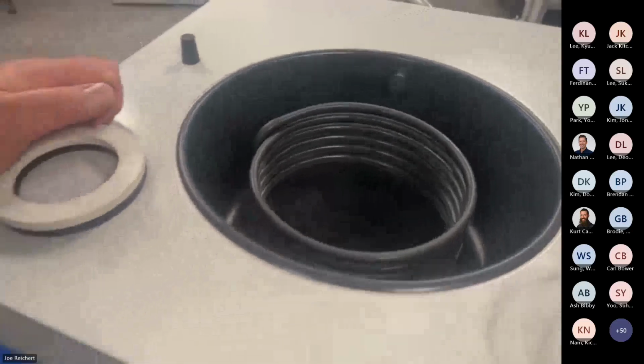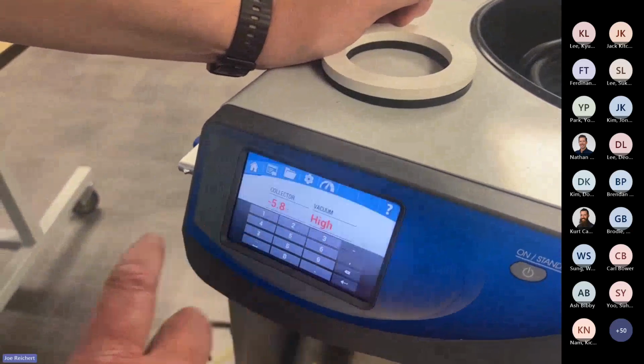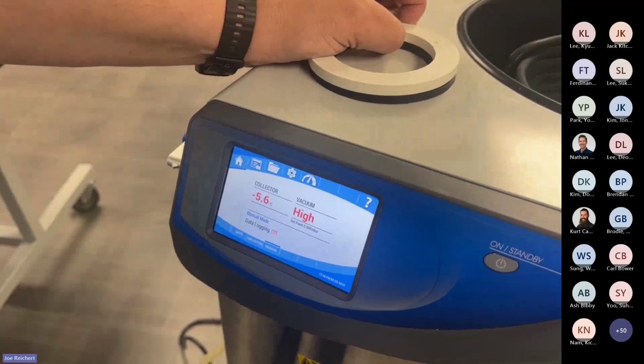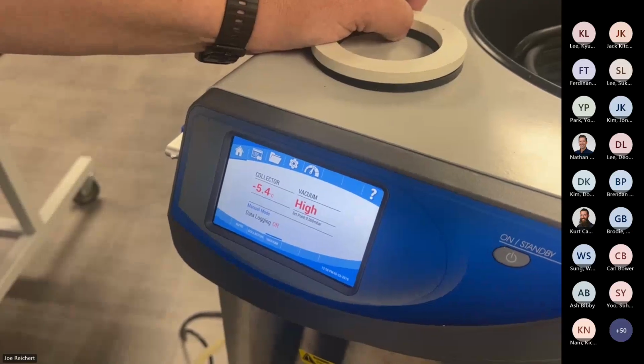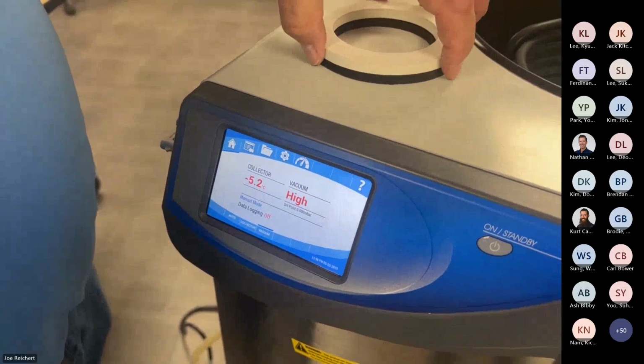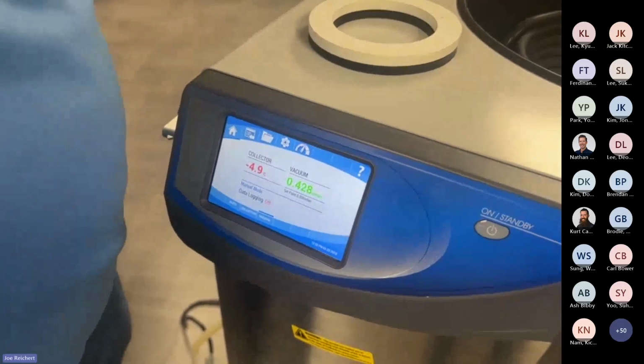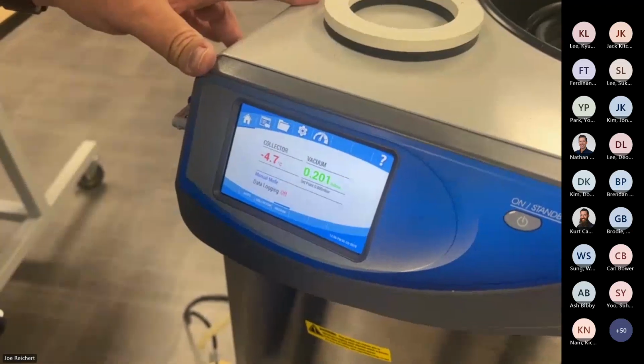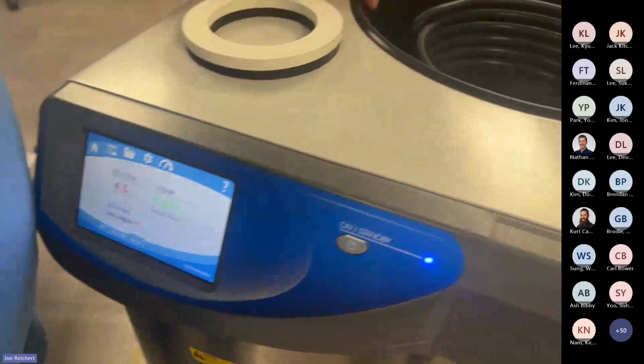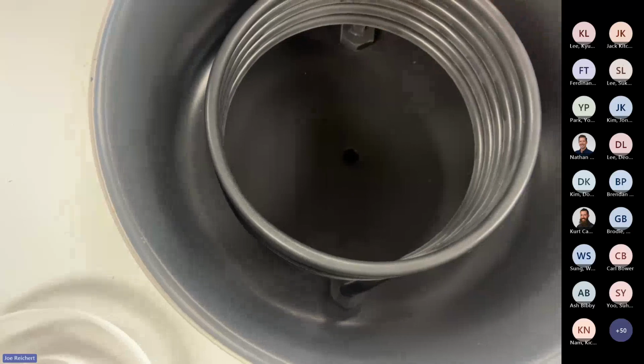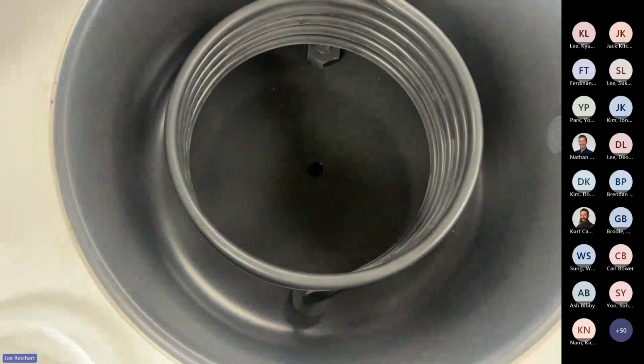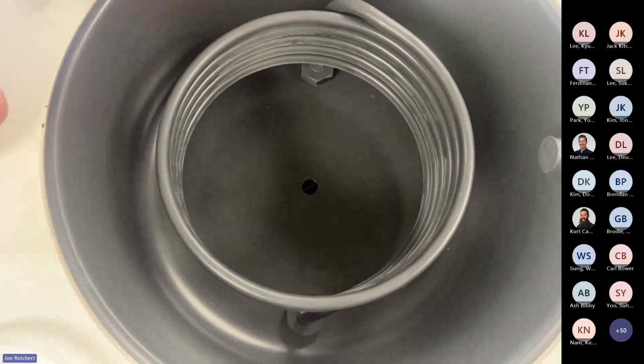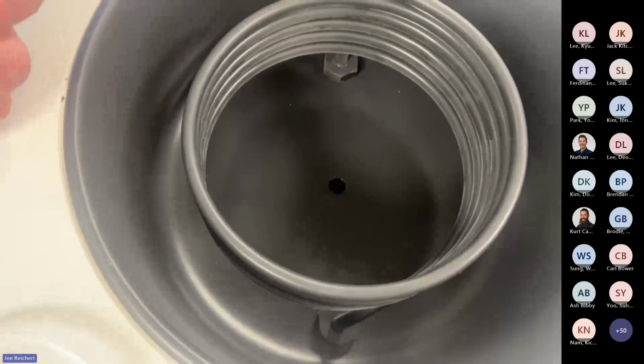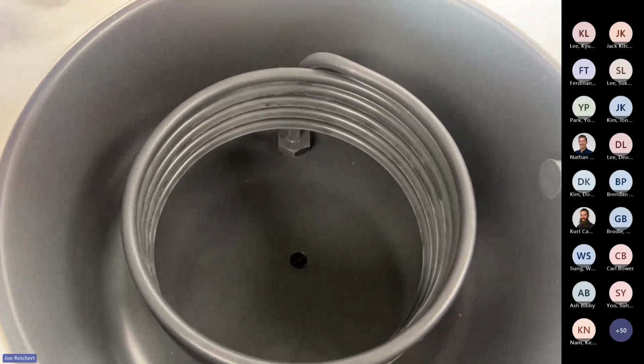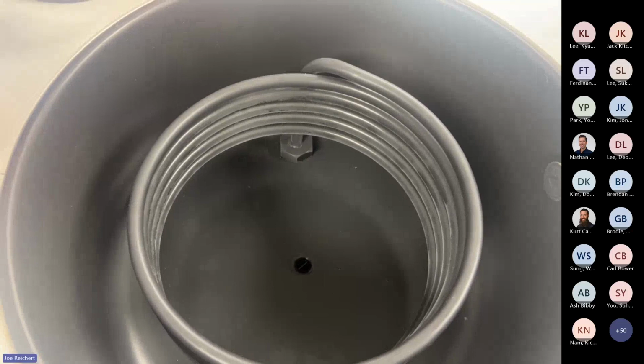And then you turn on your vacuum. And you should get a pressure almost immediately because all you're pulling a vacuum on is the hose. The pump came on. And now we start to get a reading fairly fast. And the only other spot within the chamber that could leak would be underneath the coil feet. And there's O-rings down underneath here. That takes having to remove your refrigeration lines from the bottom, removing the gas from the system to change out the two O-rings from underneath there. That's a pretty large job to do. Luckily, it's not something that we see very much at all. It's a very seldom thing you would ever see from that.